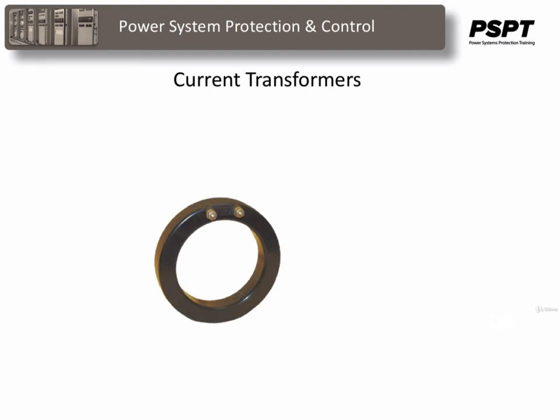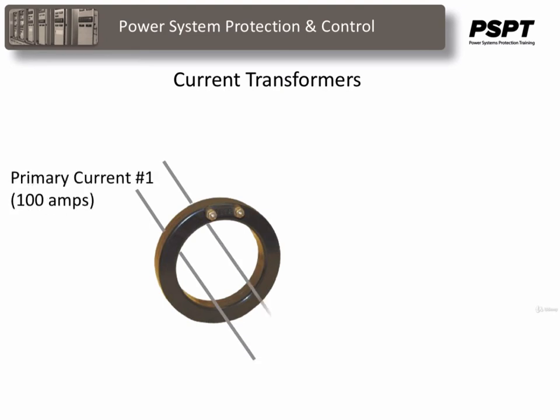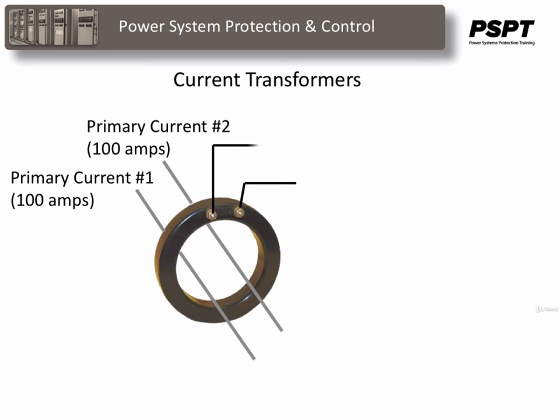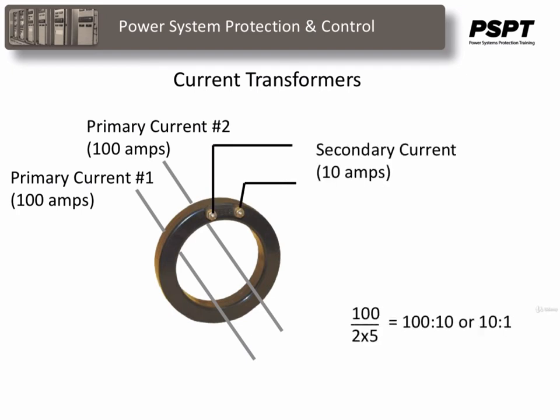Looking at it another way, the CT sees two primary wires and sees a total of 200 amps flowing in the primary. Therefore, the secondary would be 10 amps. The transformer ratio then would be 100 to 10, or 10 to 1.